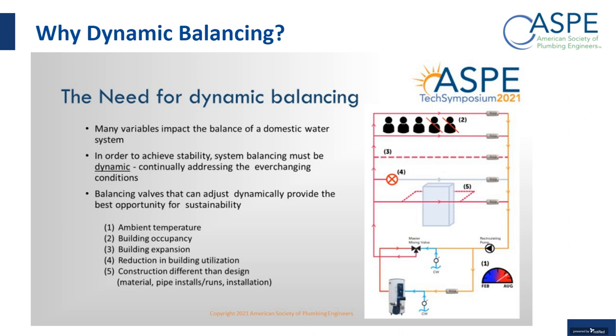So one situation could be ambient temperature. If you're in the northeast part of the country or in the Midwest, and you have some risers maybe along the outer wall of a building, and maybe they're not that well insulated, in February you could have temperatures of, say, 40 degrees in that chase supporting those risers, or you could have temperatures up to 90, 95 degrees. That's a big delta T as far as the ambient temperature goes, and that can have a significant impact on the balancing or the flow required to offset the heat loss.